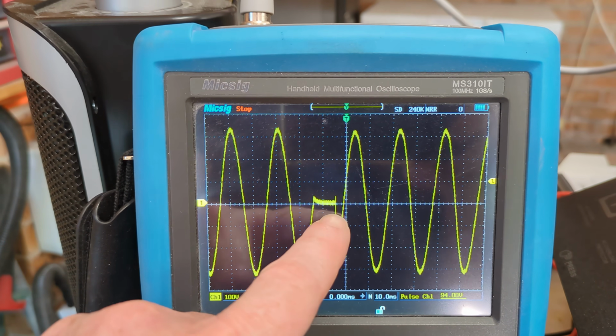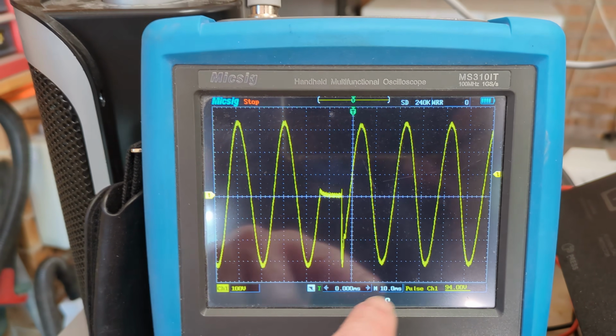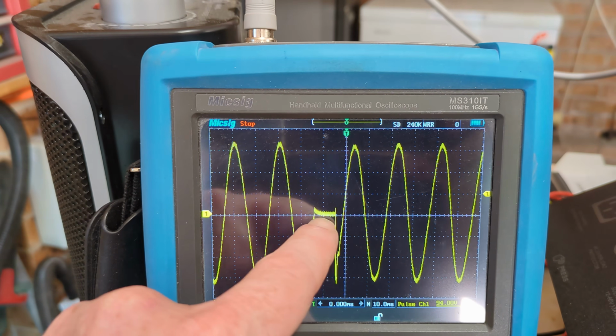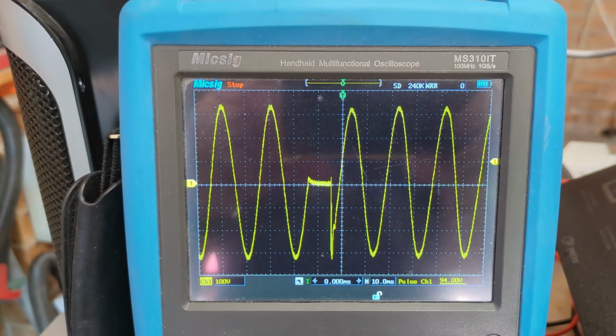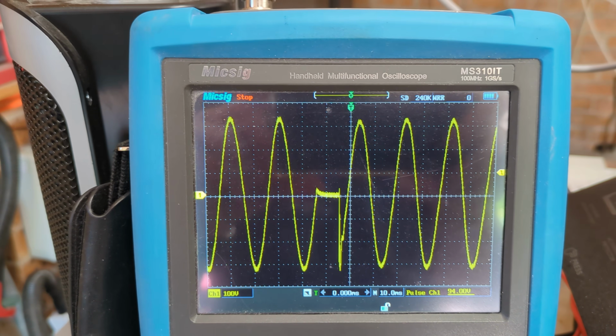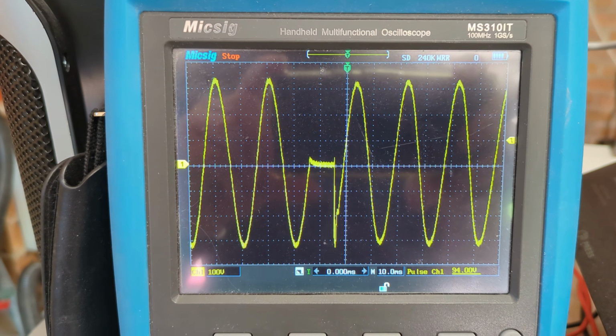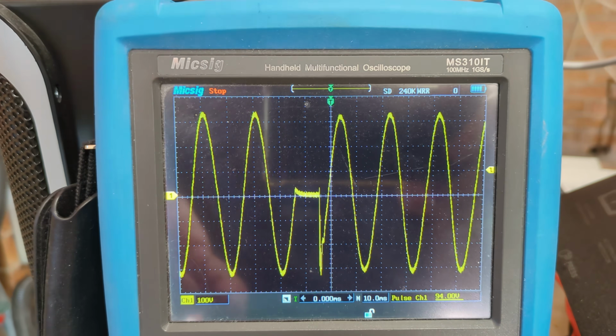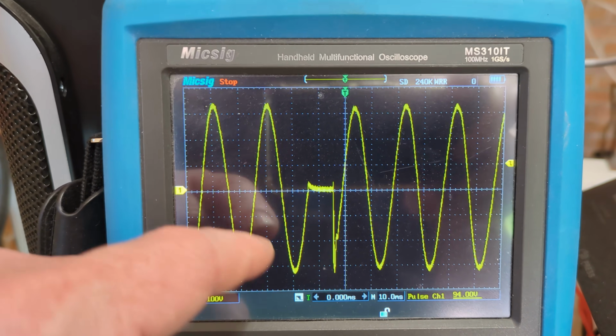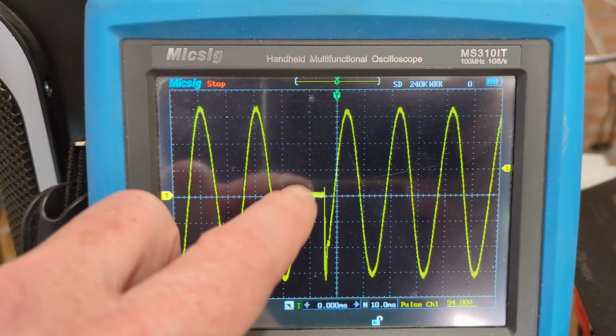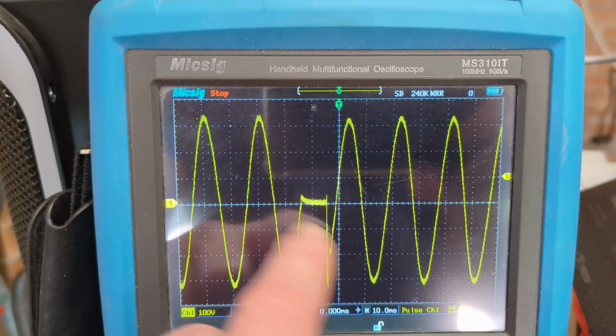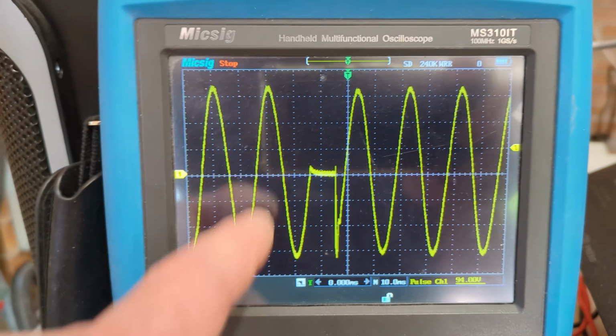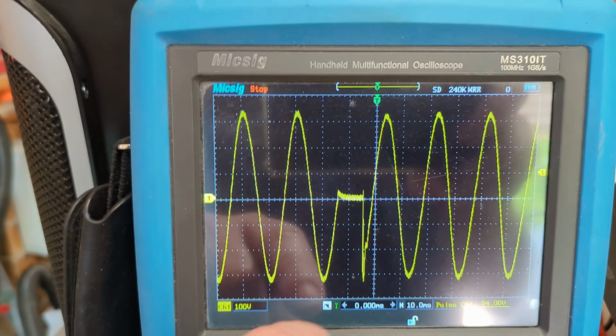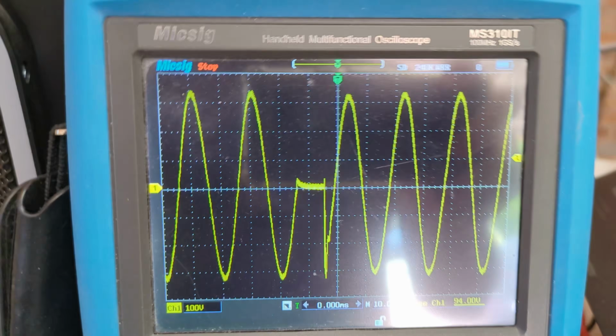There you go, I captured it with pulse triggering. This is 10 milliseconds per division, and there's a switch there when you go from battery to mains. So be aware of that, because I've had an issue here, and you've seen in a previous video with my EcoFlow Delta where this had exactly the same issue - and it meets spec, by the way. The manual tells you it has a changeover period. So expect to lose a cycle or something.